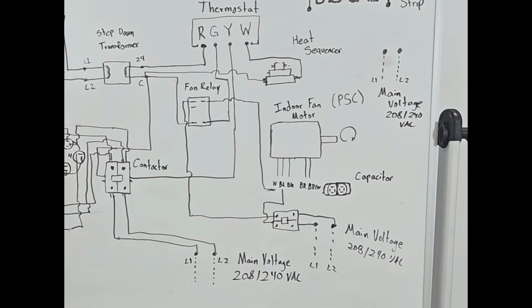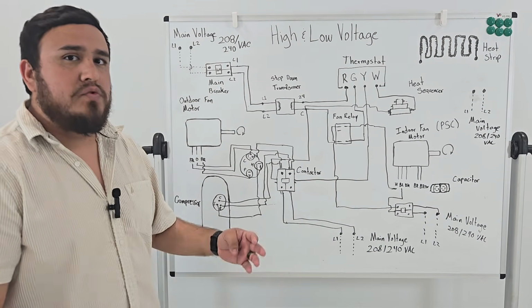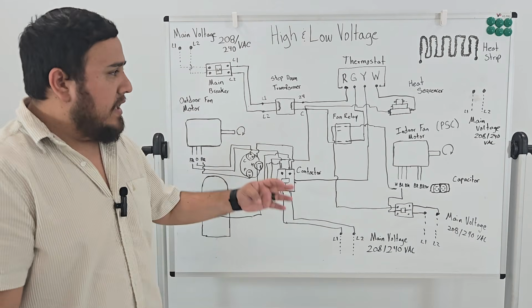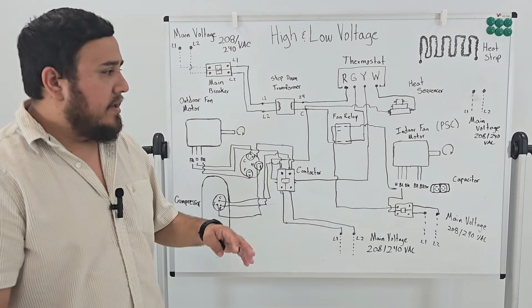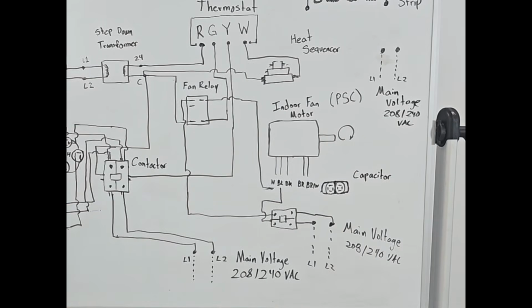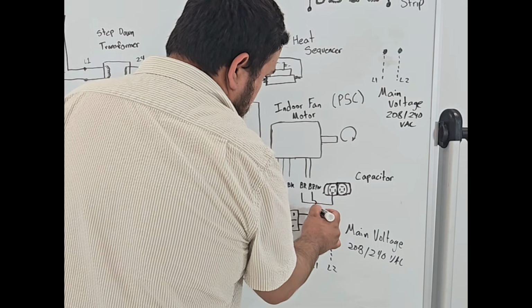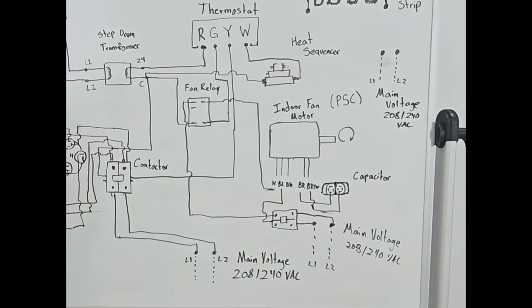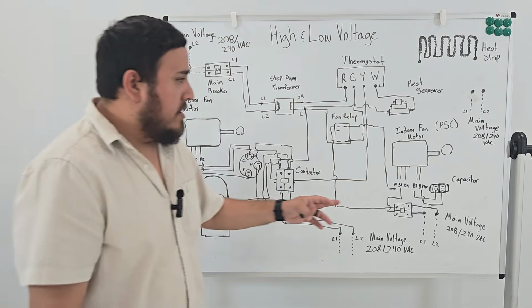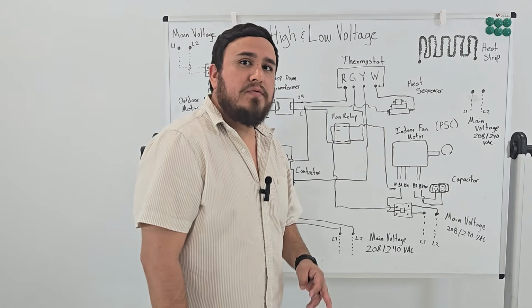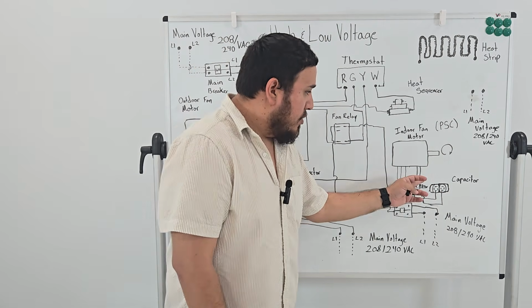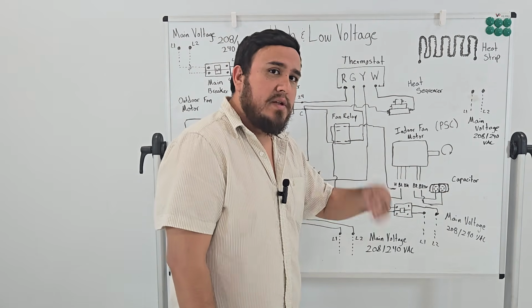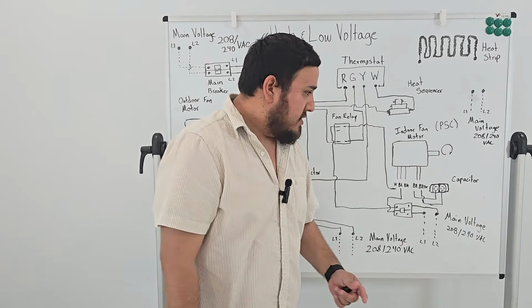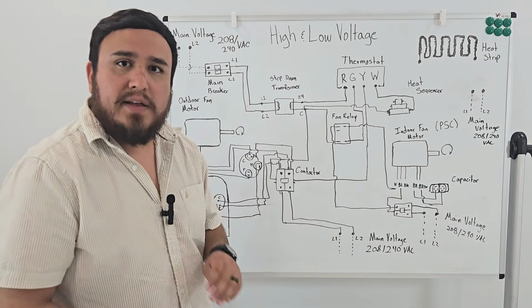That one goes direct, connected directly to line 2 voltage. After that, I'll connect the brown and brown-white wires. Remember, one has to connect on one of the four terminals for the capacitor, and the other brown-white wire connects to the other side of that same capacitor. Now we've successfully connected the indoor fan motor.